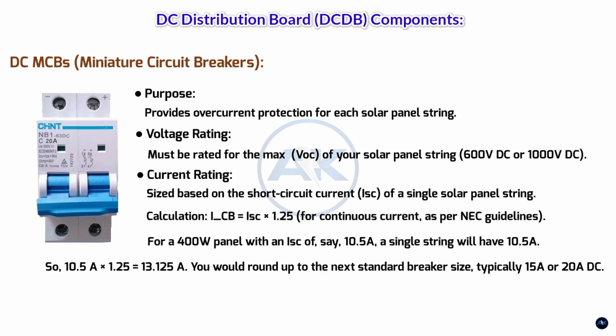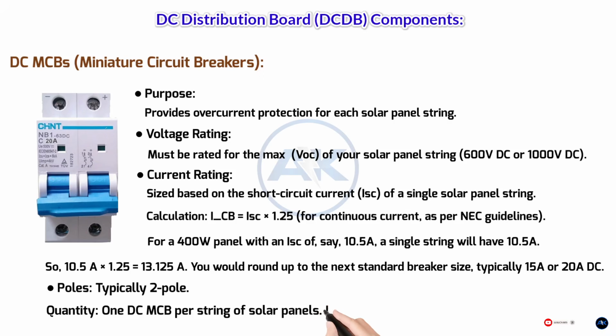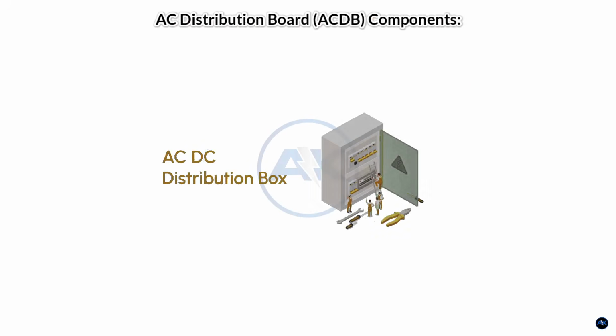If you have two strings connected in parallel before the breaker, less common in a simple DCDB, usually each string gets a breaker. You'd sum their ISC. Poles, typically 2-pole. Quantity: 1 DC MCB per string of solar panels. If your inverter has multiple MPPT inputs, each MPPT input might have its own breaker in the DCDB. AC distribution board, ACDB, components. The ACDB manages the AC power from your inverter, connecting it to your home loads and the utility grid.